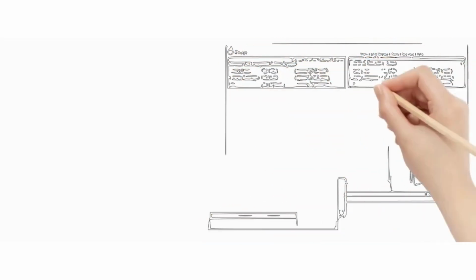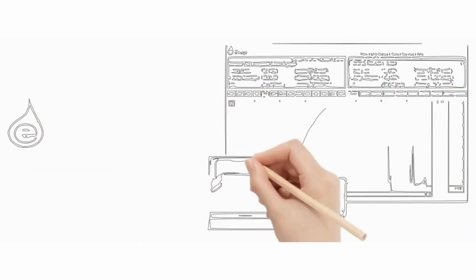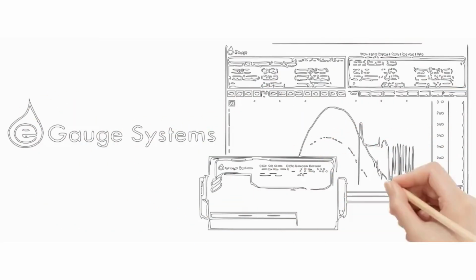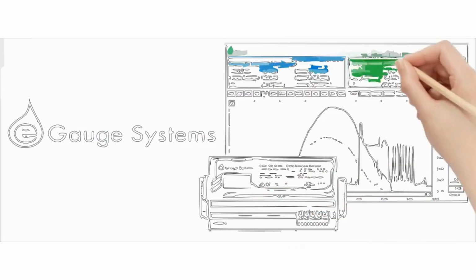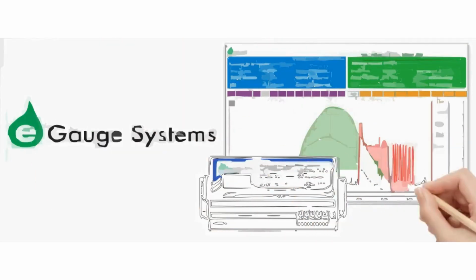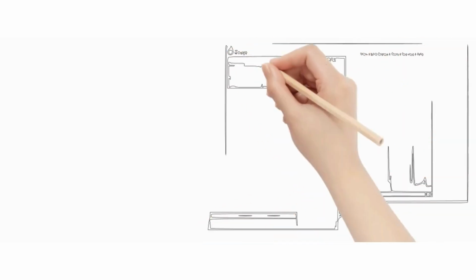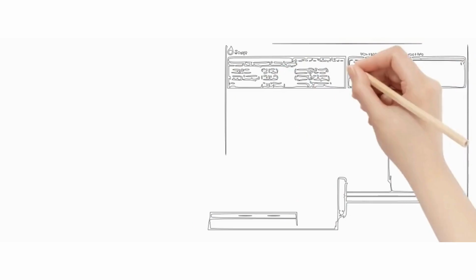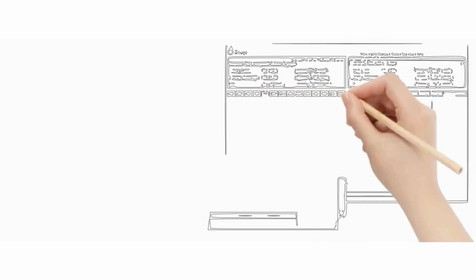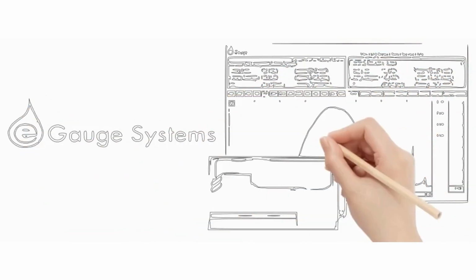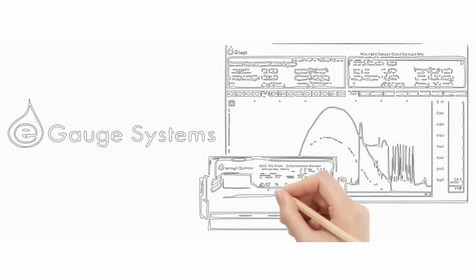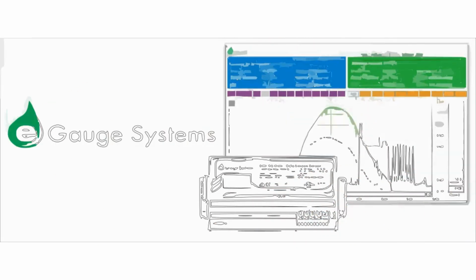So that's the flow. But how does the measurement itself work? You're dealing with potentially huge amounts of electricity. That's where the clever hardware comes in. You can't hook a meter directly to a massive industrial line, so you use current transformers, CTs, and potential transformers, PTs. Their job is to scale down those big currents and voltages to safe, measurable levels.